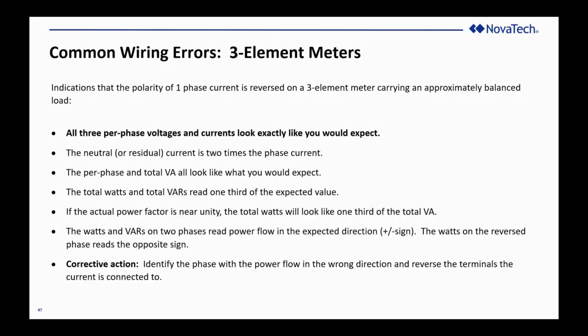I want to call to your attention the first bullet on every single slide for the rest of this presentation: all three-phase voltages and currents look exactly like you would expect. When you invert the polarity or you rotate the phases, the currents will not indicate that you have a problem. Only the watts will indicate you have a problem, and the VARs and the power factor and the per phase watts will tell you which one to look at. So all three-phase voltage and currents look exactly as you'd expect.